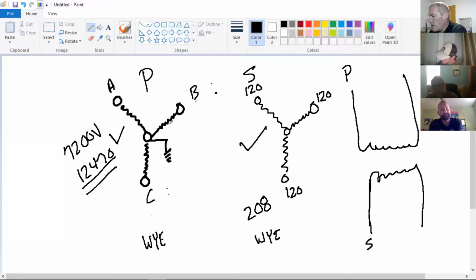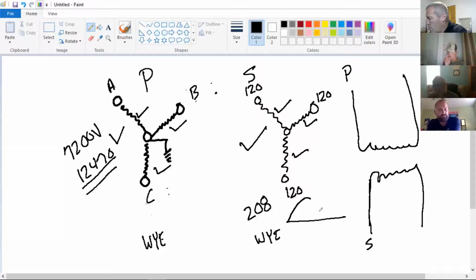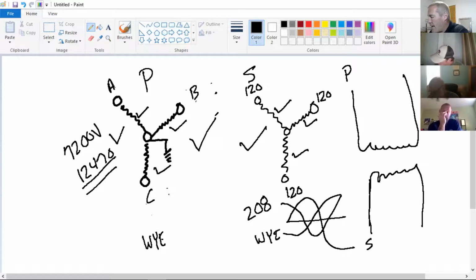Once we have introduced a different primary phase, our secondary is also going to be affected by the addition of the extra phase. You bounce all this back to try to get the relation of why we're getting 12,470 and why we're getting 208. It all comes back to: I'm not getting full power out of all three phases at the same time. I'm only getting 1.7325. The thing to remember here is it happens on the primary side and secondary side of the transformer. That effect goes through the entire process.